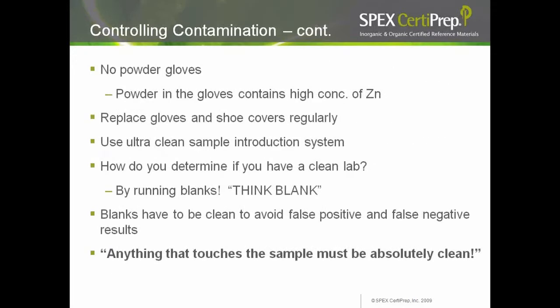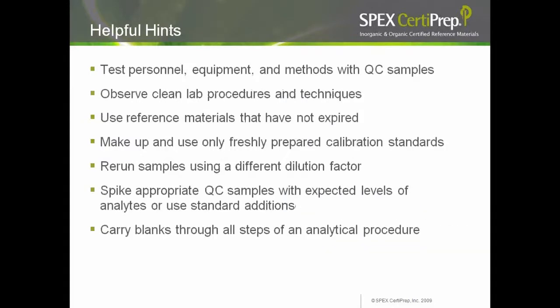Select gloves that have no powder — powder in gloves contains high-concentration zinc. Use ultra-clean sample introduction systems. How do you determine if you have a clean lab? By running blanks. Blanks must be clean to avoid false positive or false negative results, and anything that touches the sample must be absolutely clean. Besides controlling contamination, test personnel, equipment, and methods with QC samples and observe clean lab procedures and techniques.